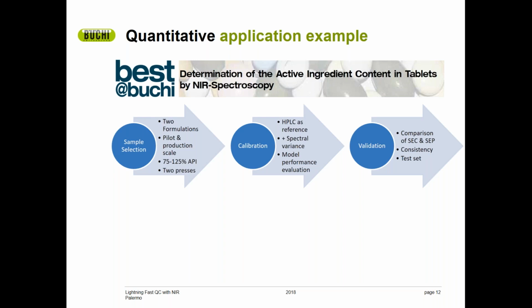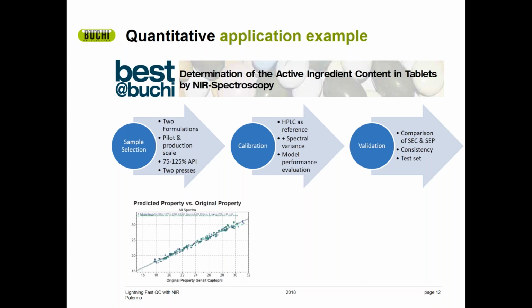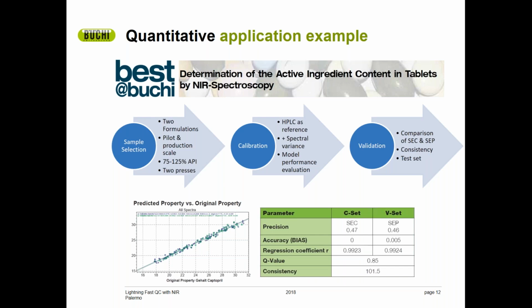For calibration work, HPLC was used as the reference for API composition. All sources of known spectral variance were considered in the sampling plan, including the positioning of scored versus unscored tablets, and by varying the tablet press used, which impacted tablet hardness. The calibration results for the 25 milligram formulation are provided in the table and graph here. Metrics such as precision, bias, regression coefficient, Q value, and consistency were evaluated for both the calibration and validation set samples.